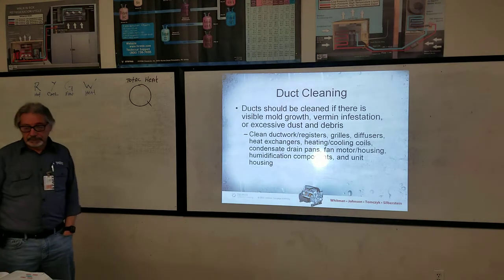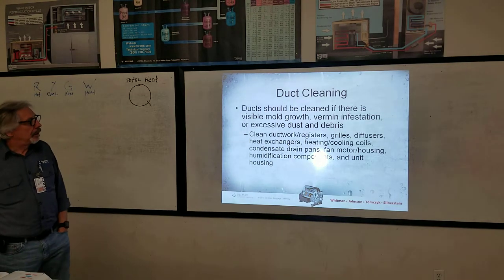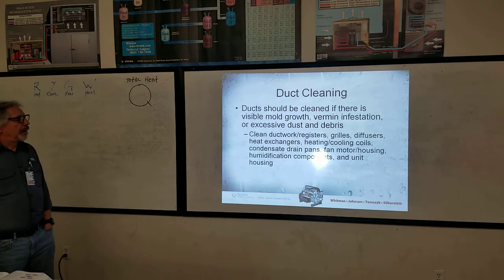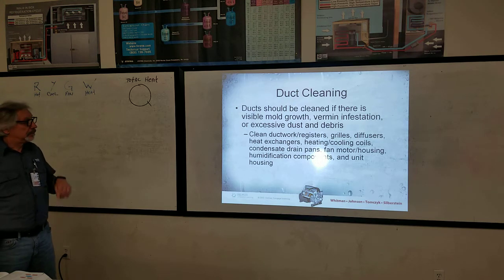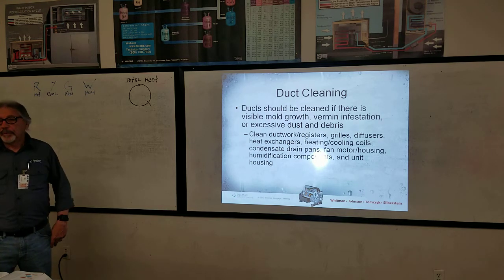Ducts should be cleaned if there is visible mold growth, vermin infestation, or excessive dust and debris. Clean ductwork registers, grills, diffusers, heat exchangers, heating and cooling coils, condensate drain pans, fan and motor housing, humidification components, and unit housing.